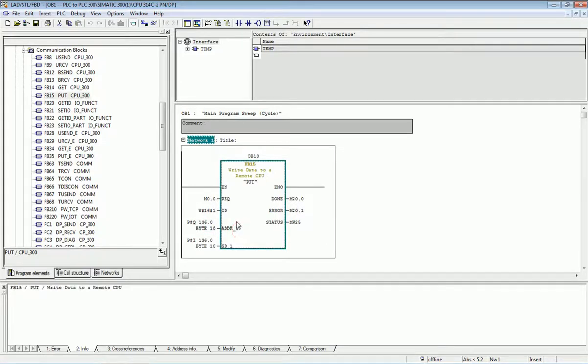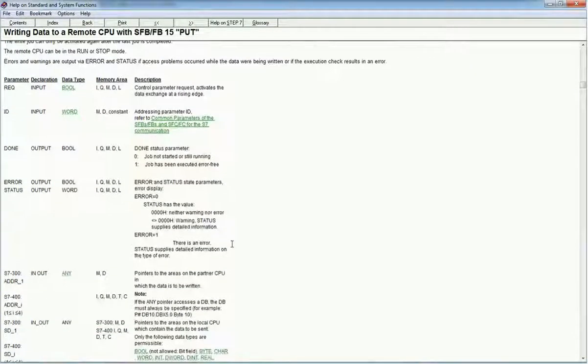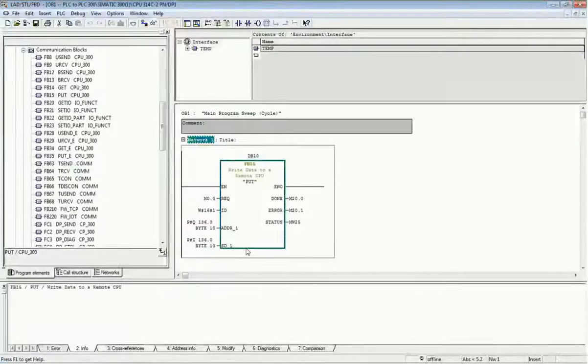The third parameter is the addressing — from where you want to fetch the data. This is the standard format in Siemens PLC for the PUT instruction. From the help menu of this block you get detailed information on how to set addressing for sending and receiving data. The pointer points to the address on the local CPU which contains the data to be sent. The format starts with P# followed by the starting bit address and the total number of bytes you want to send.